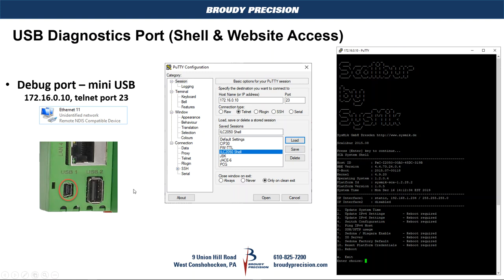As we've shown in our previous Tech Tuesday video, the ILC 2050 has a USB diagnostic port labeled USB 1, which is a mini USB port used to access shell and also gives you browser access to look at the IO that's in line with the controller and also to see and change the various settings of the ILC 2050. The basics of it is you're connecting with a mini USB cable, and when you connect to the controller with your laptop you're actually going into a telnet session.